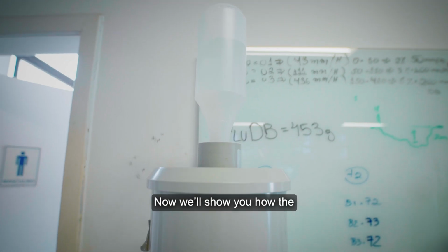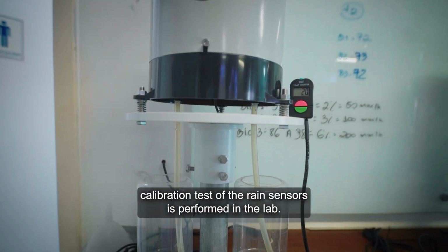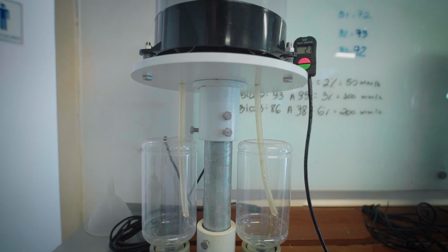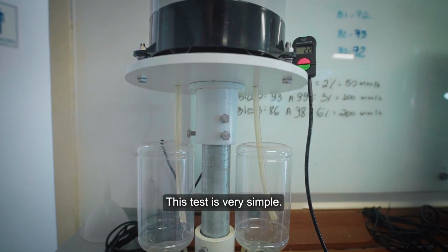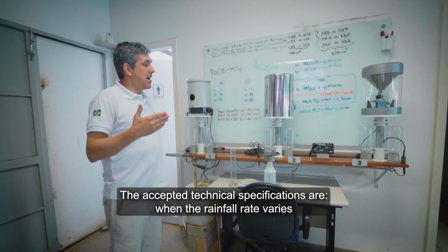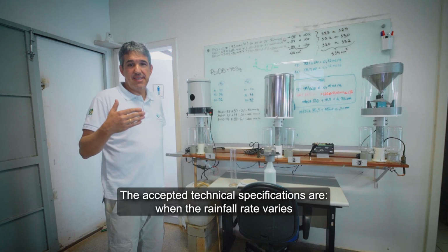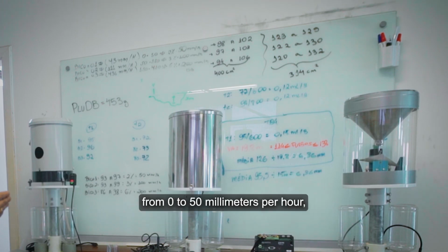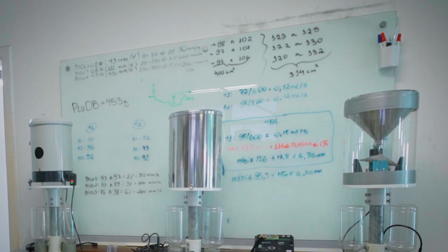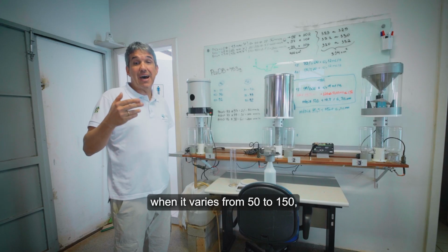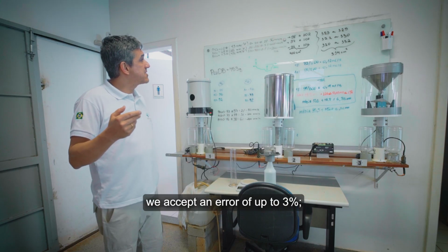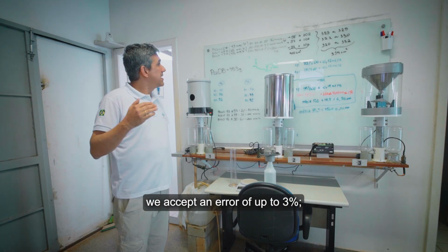Now we'll show you how the calibration test of the rain sensors is performed in the lab. This test is very simple. The accepted technical specifications are: when the rainfall rate varies from 0 to 50 millimeters per hour, we accept an error of up to 2%. When it varies from 50 to 150, we accept an error of up to 3%.